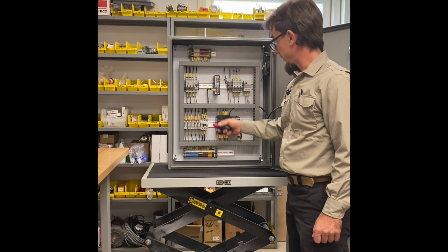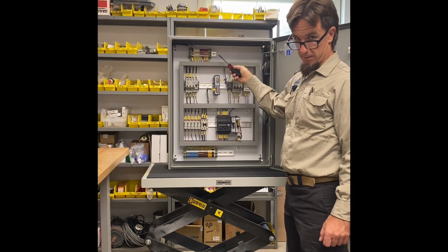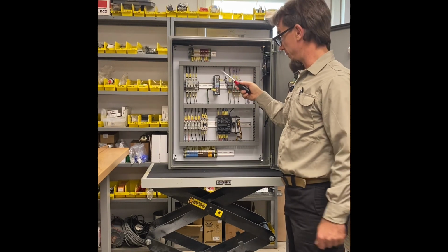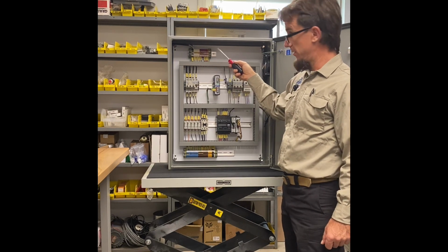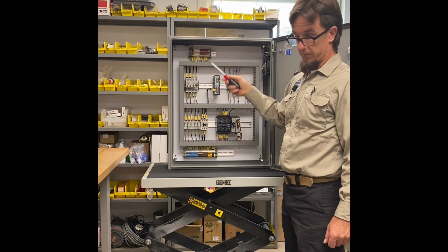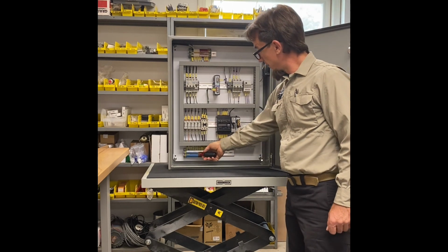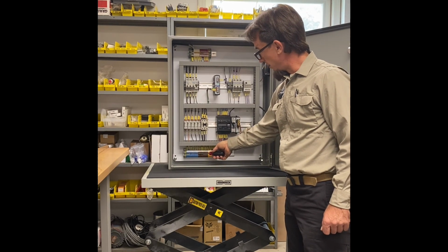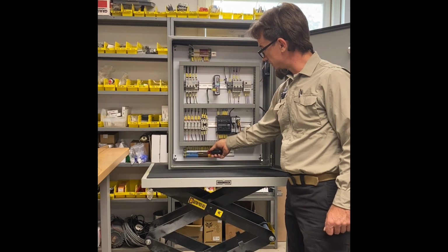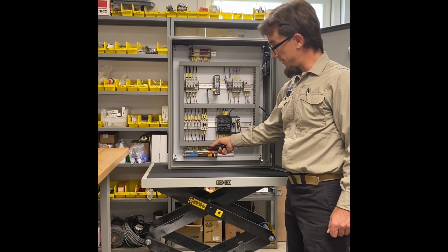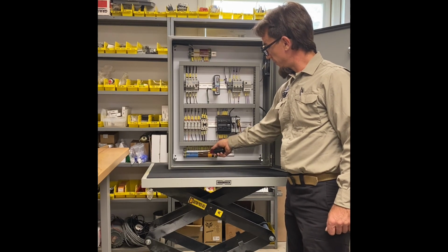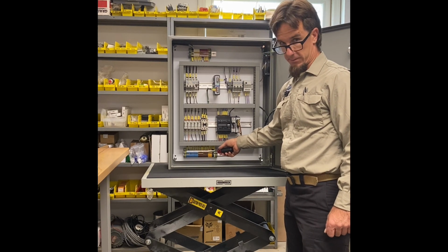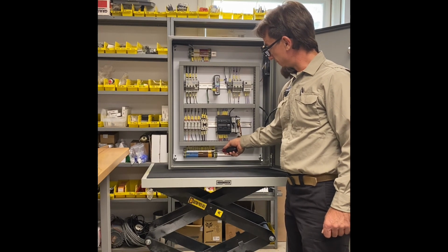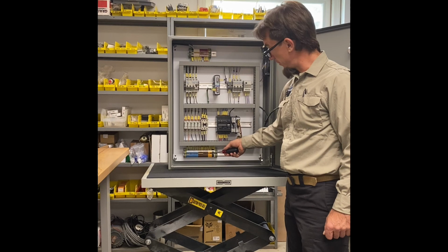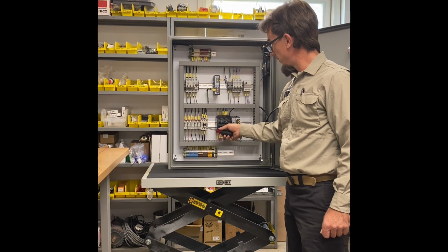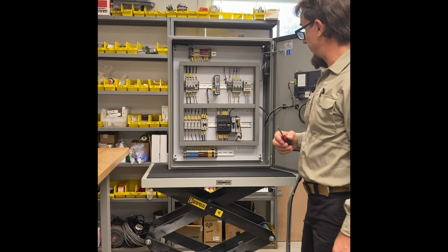Now you'll notice I use different colors on each of these, and again, some of this is because I won't be the installer and I want to make it as simple as possible for the person installing or the person that's doing the troubleshooting many years down the road. So the blue section of terminal strips here are all of my inputs and outputs to the 3 motors, well number 1 and the 2 high service pumps. The browns are for the 5 floats in the ground storage tank. The yellows are from the pressure switches that will control the high service pumps, and the black is for the booster pump output.